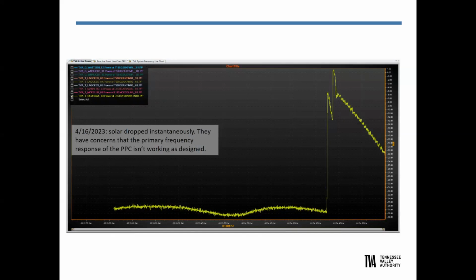And again, the first event was caused by a fault on the power system that dropped their voltage. They had a momentary dropout to zero. They slowly recovered. We asked them to investigate the 10 megawatt per minute increase ramp rate. And when they did that, they overcompensated. So then for any twitch, they'd drop out essentially.